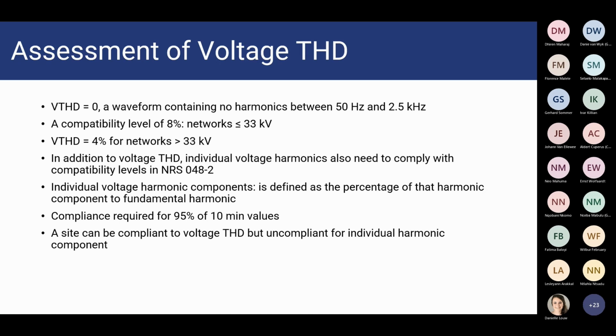And this is something that we have seen from our experience that is very important in distributed generation, where the THD is used as a value to spec your equipment, like the transformers, and the inverter manufacturers do not define the higher harmonics, which also need to be taken into account when designing and speccing, for example, the transformer. So it's very important to take note of that.